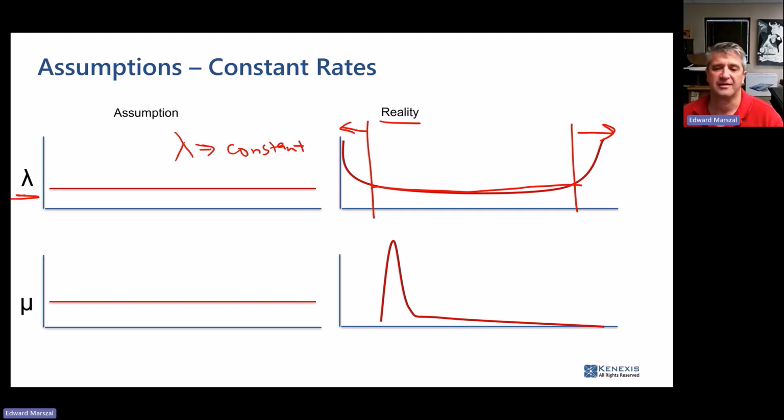Okay, that's reasonable. But in a Markov model, well, pretty much any of the reliability models that we're using, the idea that the repair rate is constant is fanciful, ridiculous. So what the Markov model is telling you is that it is just as likely that I will repair my device at hour number 1 as I will at hour number 100. That is ridiculous. That does not match reality in any way, shape, or form.